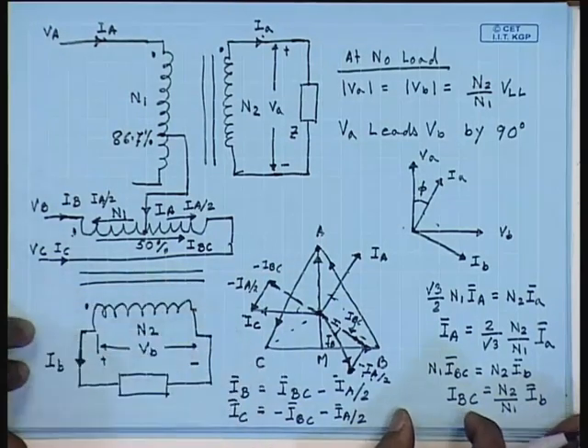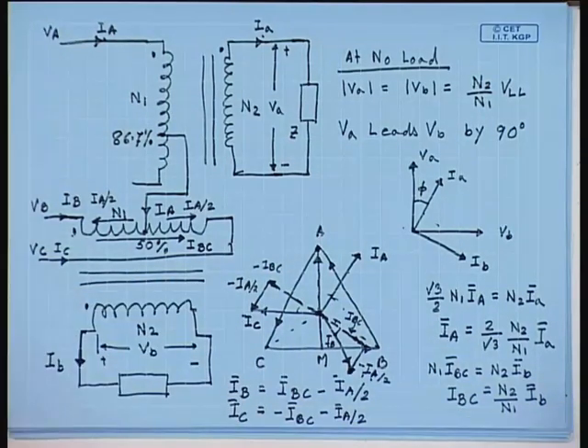So we see that when we put a balanced three-phase to two-phase load on the Scott-connected transformer secondary at an arbitrary power factor, not necessarily unity power factor, the three-phase side currents are also balanced.